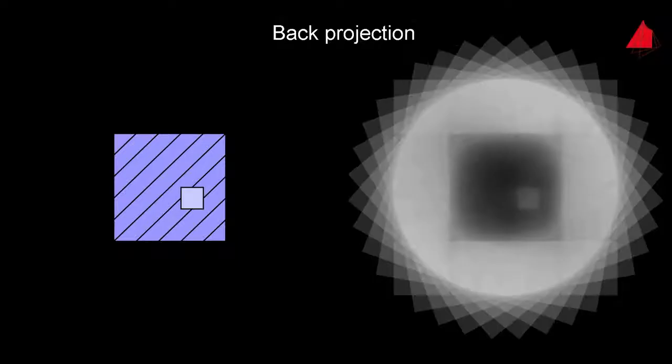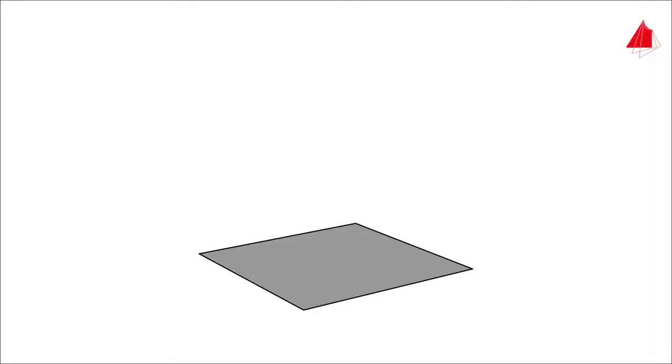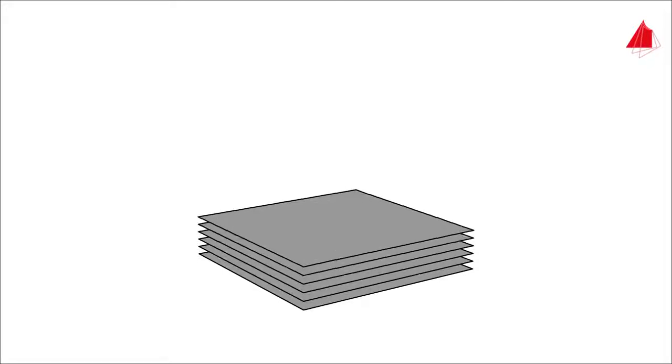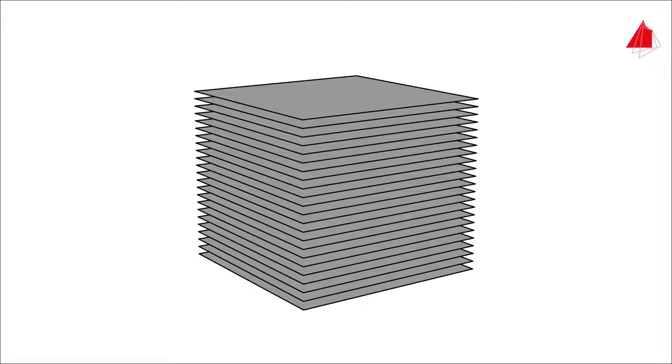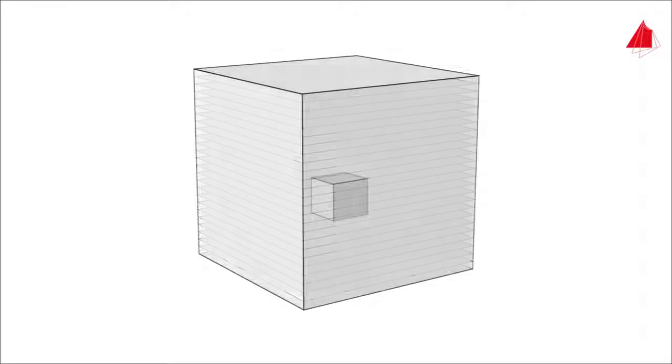Displayed as a positive image, the back-projected plane looks like this. Much better results can be achieved with appropriate filter methods and with even more images. The back projection is carried out successively for each sectional plane, until finally a three-dimensional model of the sample is generated by the computer. Using sophisticated visualization methods, the sample can be examined in detail on the computer display.